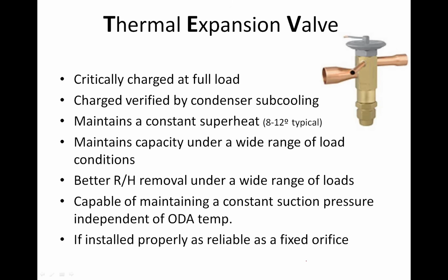I hear time and time again, oh, I hate TXVs, they're horrible, I have a lot of failures. Well, TXVs are a precisely manufactured piece of equipment. If you're going to install high efficiency equipment, you've got to use correct practices. That means you do a proper evacuation and a proper installation. Tubing has to be deburred, and those burrs can't end up in the tubing. The system should have nitrogen purged through it when you're brazing it, because copper oxides can plug up the inlet filter to a TXV. That filter dryer needs to be installed at the time of installation. If you do the steps properly as you install the system, the TXVs almost never fail.